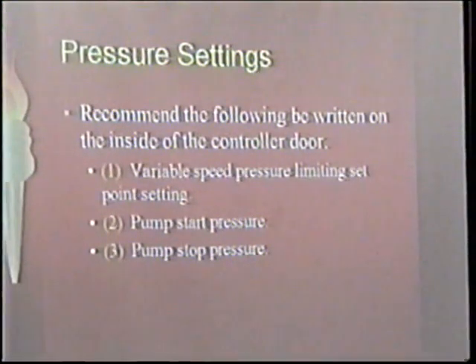I recommend the following be written on the inside of the controller. This is actually in the new code as a mandate on variable speed pressure limited controllers. It does not mention it outside of that type of controller. Mark and I have been trying to do this for some time on the jobs where we do startup, because if anybody has to come do maintenance on it, they need to know what the set pressures were at startup. So that's where this log is kept. So we just try to write it on the inside of the door in an indelible marker.